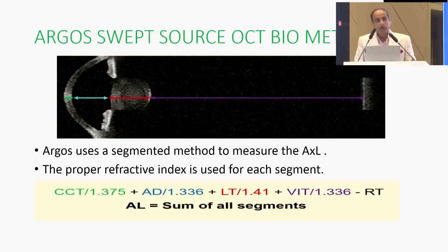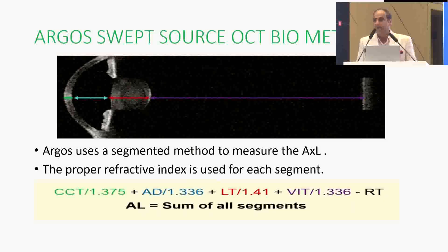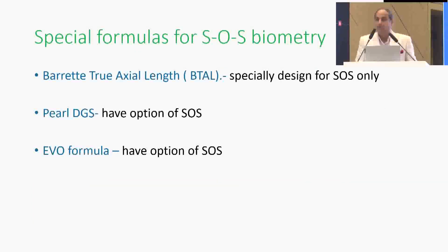Another new tool in the market is the Argos swept-source OCT biometer. What is unique about it is the sum-of-all-segments approach. It uses a segmented method for each part of the axial length, because different structures have different refractive indices. The Argos measures axial length specifically for each segment of the eye, and the axial length becomes the sum of all segments, or SOS. Special formulas for this biometer include the Barrett true axial length, or BTAL, specifically designed for SOS, as well as PEARL, DGS, and EVO formulas.